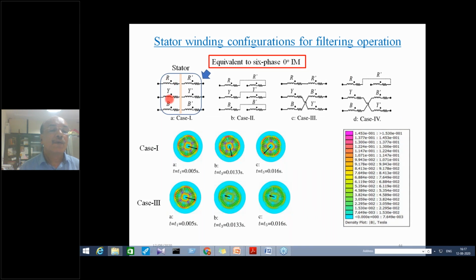Here one winding is R, Y, B, and the other is R-dash, Y-dash, B-dash. These give 3 terminals on one side and 3 terminals on the other side, so you have 12 terminals in total. If these 12 terminals are connected as in case 2, you can see they are connected in series - here series, then a cross, then series again, but with a cross.